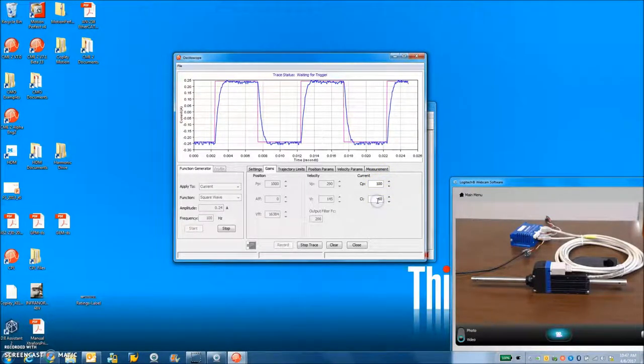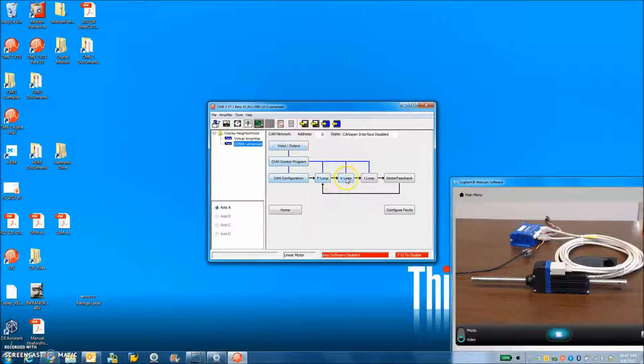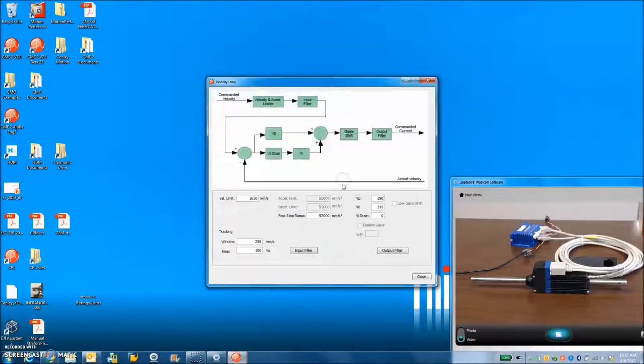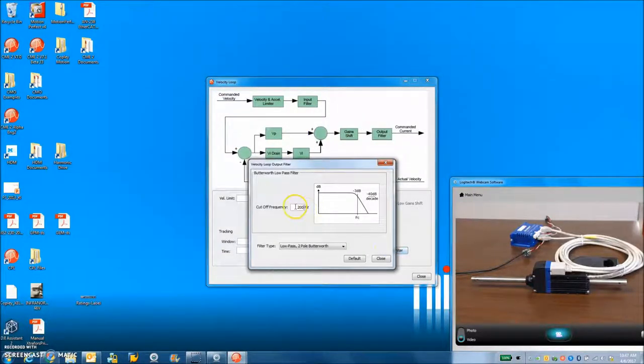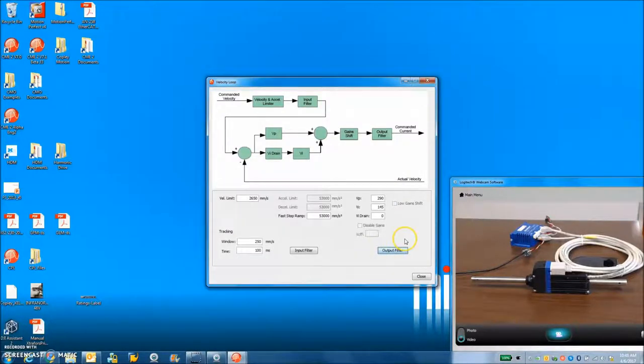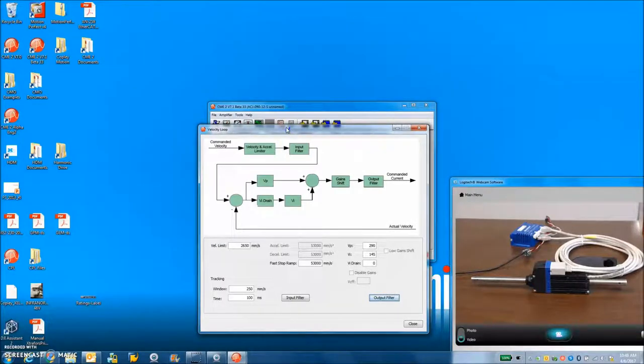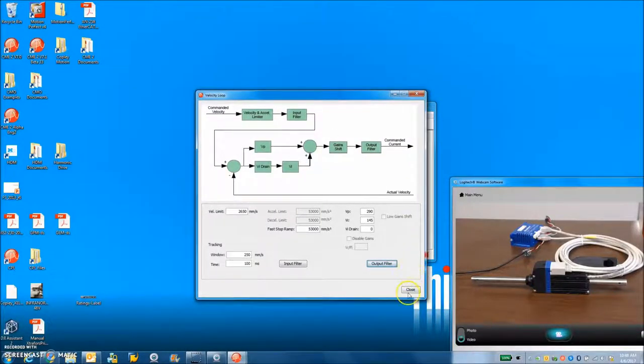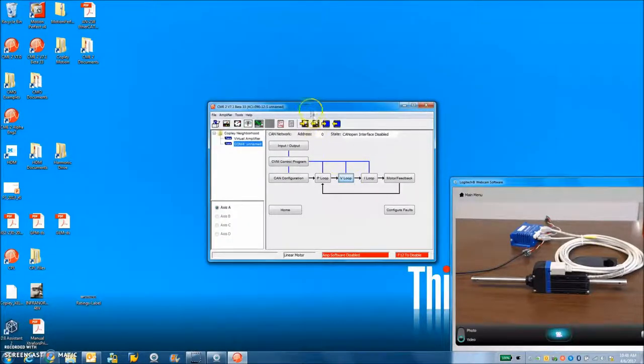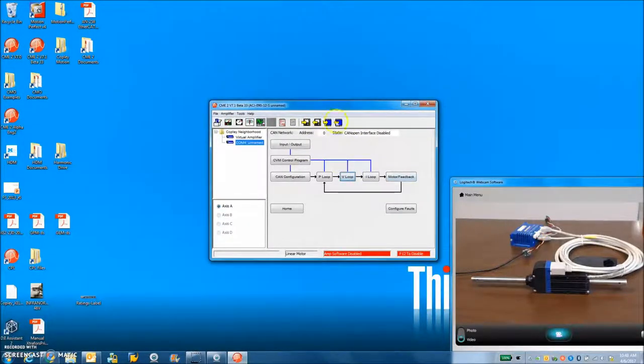So I could probably get a kilohertz current loop bandwidth out of this if I want, which is nice if I'm pushing the velocity loop real hard. So yeah, there is a pole output filter at 200 hertz, low pass Butterworth. I'm going to do a single pole. This is an older drive configuration. The plus drive has fancy filters and more configuration. So I'm just limited by the old ACJ here, which is fine. We're able to do really good control with that.